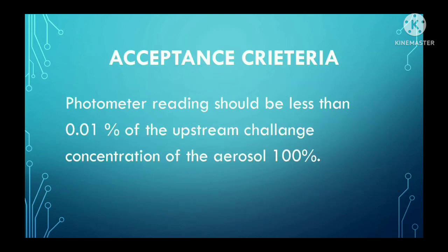Now we will see the acceptance criteria for HEPA filter integrity test. The photometer reading downstream of the HEPA filtration unit caused by leakage should be less than 0.01 percent of the upstream challenge concentration of the aerosol.